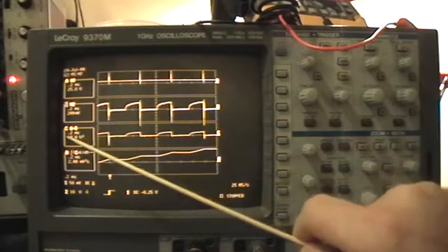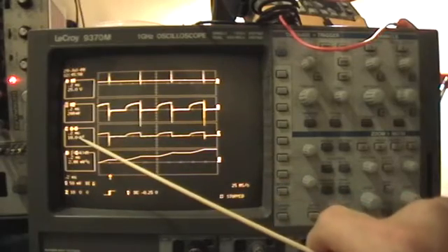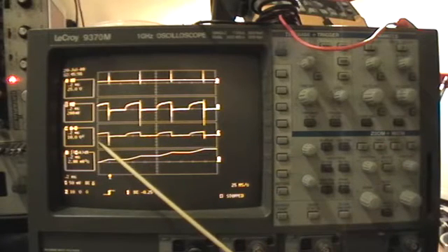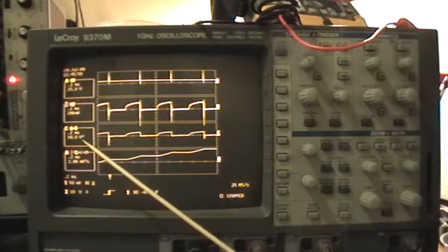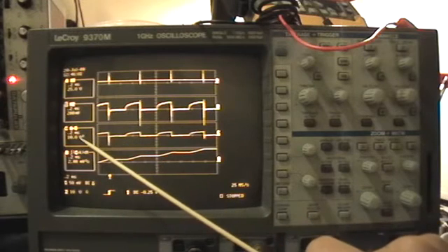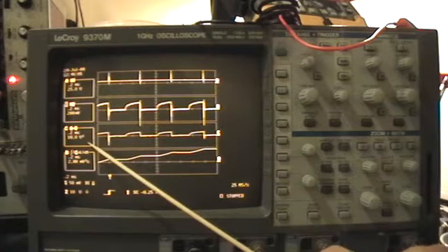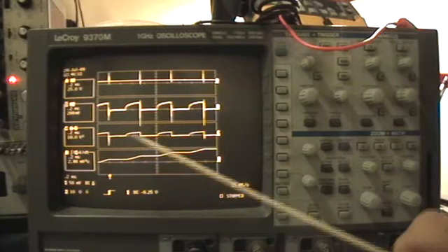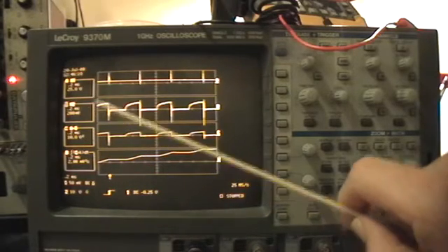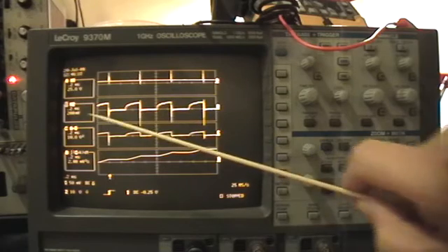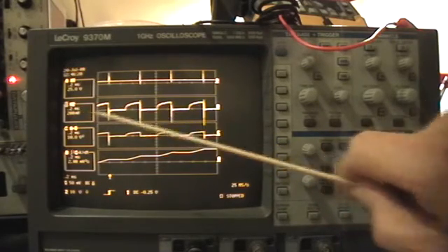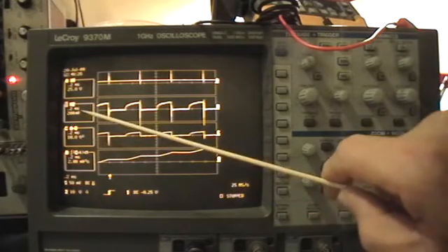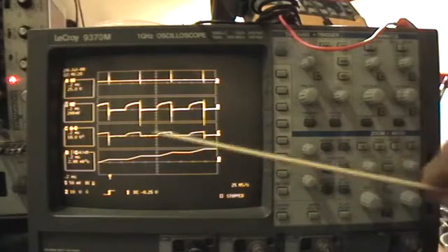Okay, down here is the instantaneous power trace that is made by multiplying these two traces together at each individual point along the way. So the instantaneous power trace, here it says V squared, but of course, since this is actually a current trace, this would be volts times amps, which is of course watts. Okay, and you can read this V squared as watts. The actual value would be 1/4 of the numerical value because we're using a 0.25 ohm current viewing shunt, right? Instead of a 1 ohm current viewing shunt. If it was 1 ohm, the values would read directly.